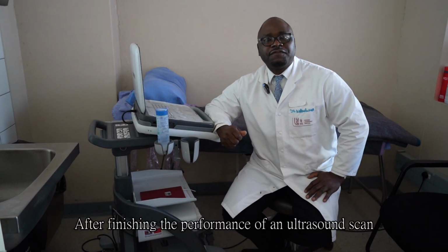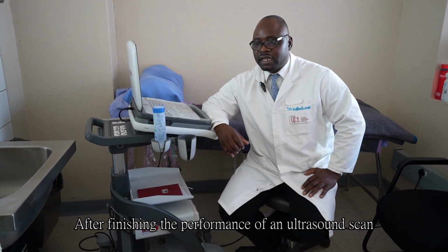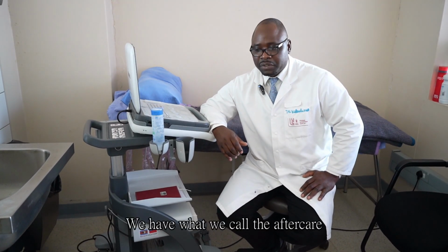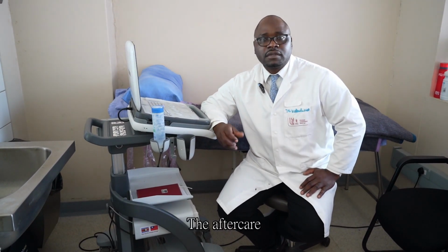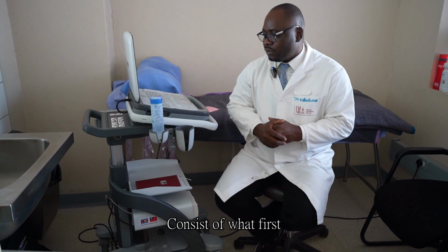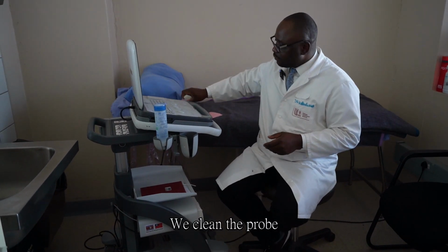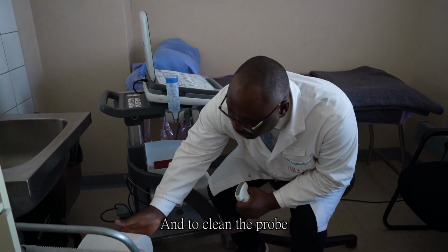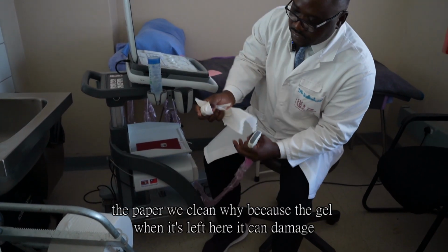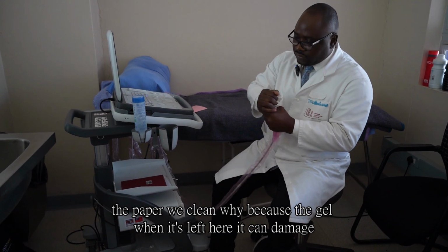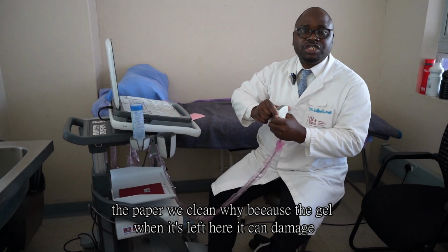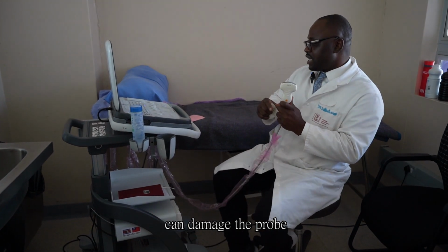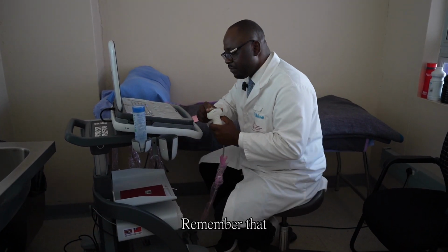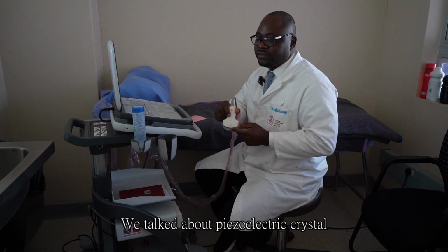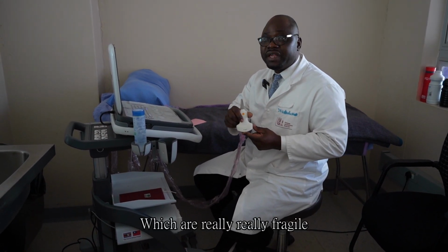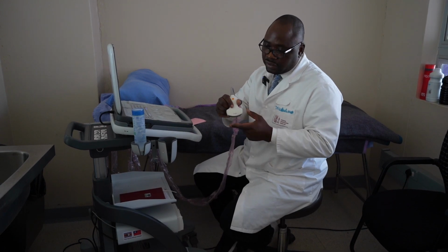After finishing the performance of an ultrasound scan, we have what we call the aftercare. The aftercare consists of what? First, we clean the probe. And to clean the probe, we again use our paper. We clean, why? Because the gel, when it's left here, it can damage the probe. Remember that we talked about piezoelectric crystals, which are really fragile, and they are in there.